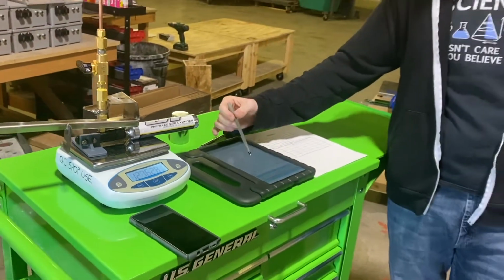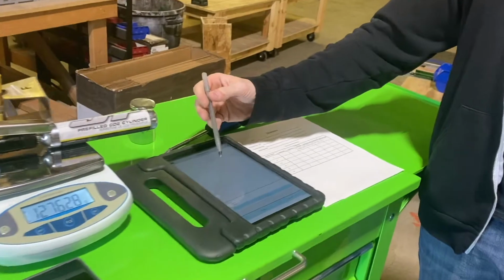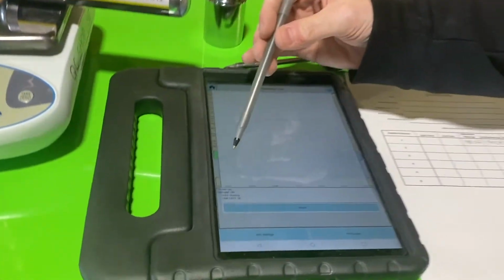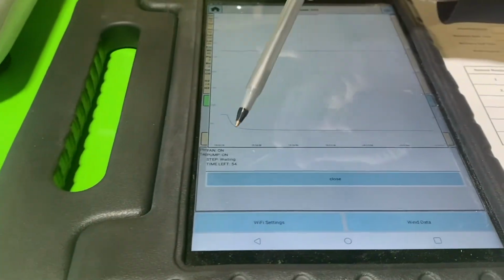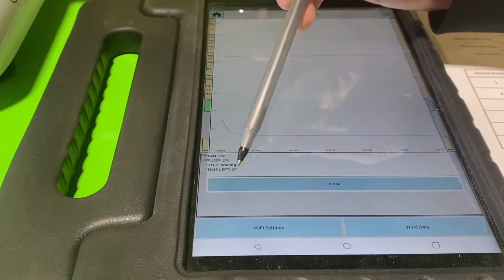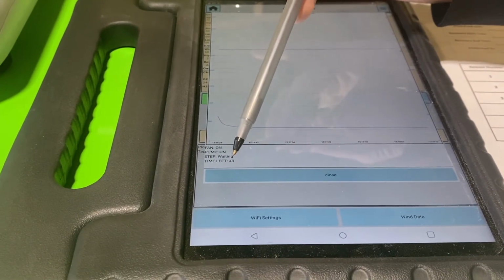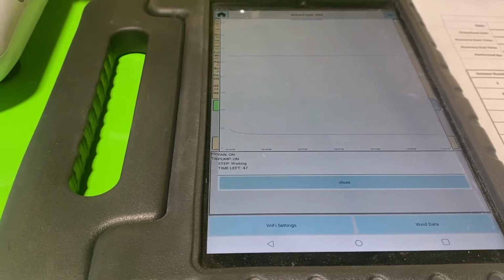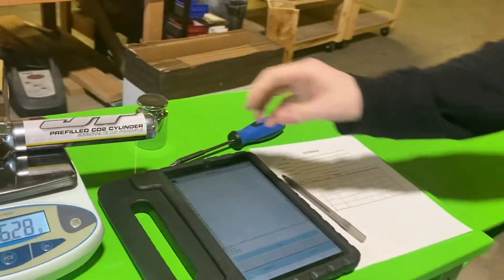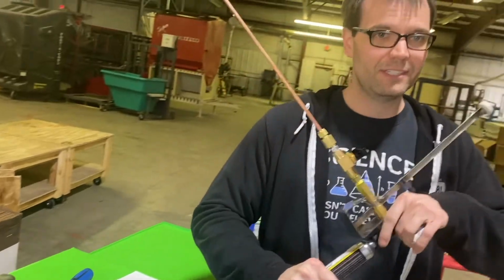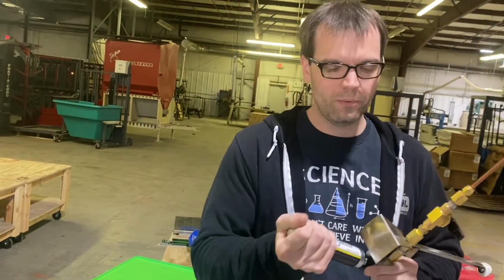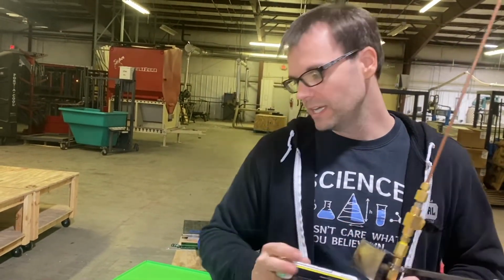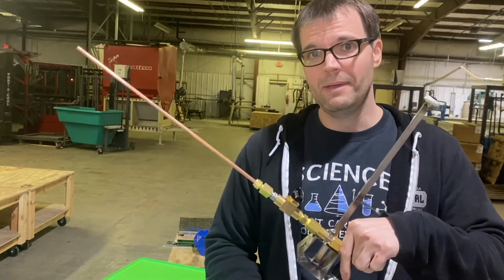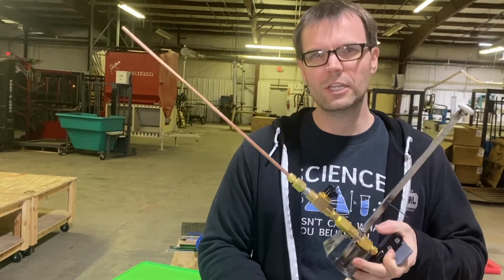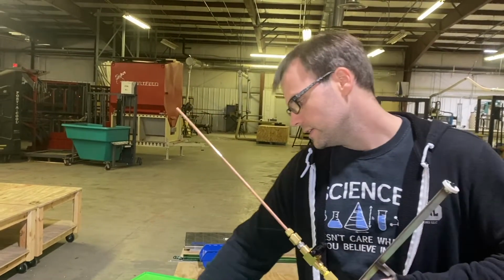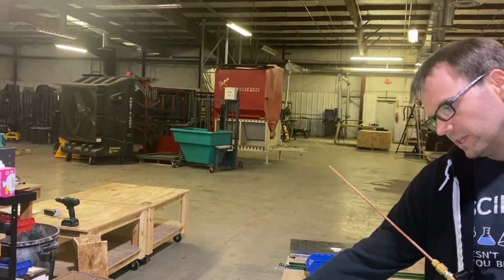Now what we're waiting for now is, during a CO2 recovery, you want to make sure that you have 3 minutes between each release. And so the control feed app is actually taking that into account. So we have 50 seconds before we're going to do our next release. During that time, like I said, this is still almost ice cold. We want to warm this up as much as possible because of adiabatic cooling, it's going to release a lot slower this next time.